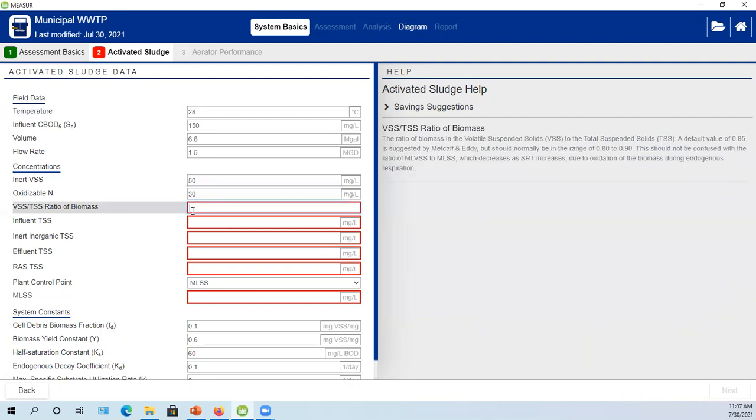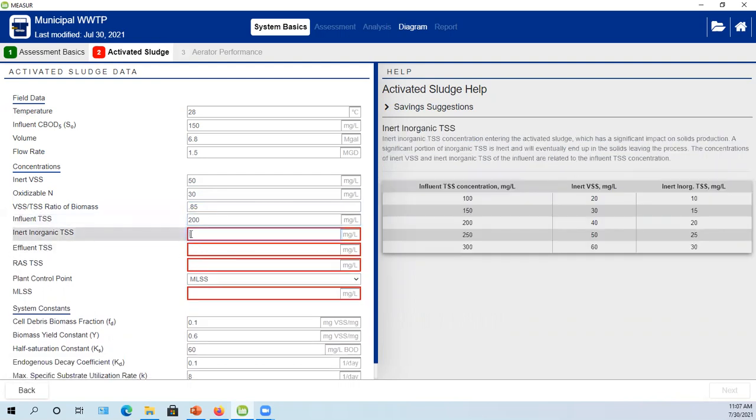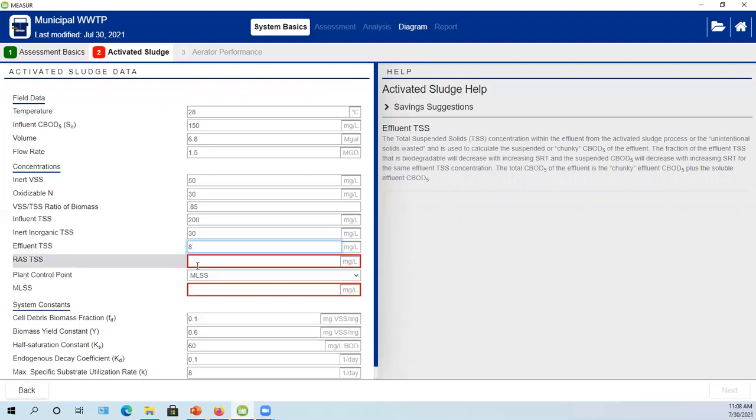The oxidizable nitrogen coming into the wastewater was 30 mg/L. VSS-to-TSS ratio is almost always 0.85. Influent TSS was 200 mg/L. For inert inorganic TSS, at 200 mg/L we'd normally recommend 20, but I went a little higher to calibrate against their solids production data. Effluent TSS was about 8 mg/L. RAS TSS concentration was 5,500 mg/L. They're operating at about 3,000 mg/L of MLSS in the aeration process, which they're trying to maintain.